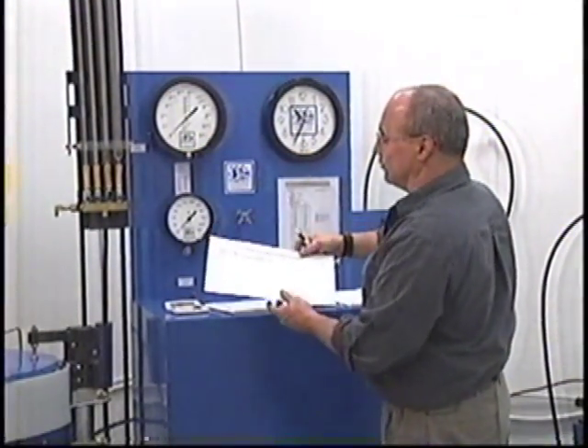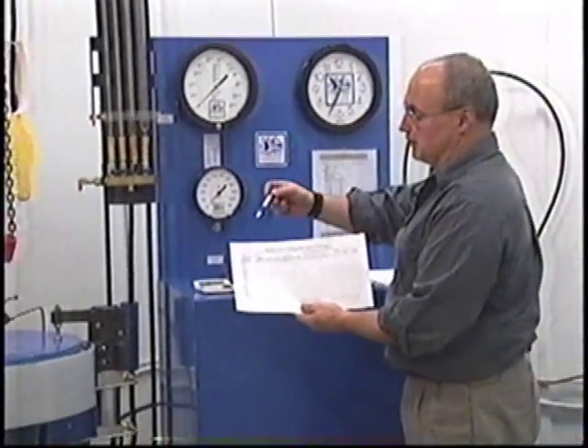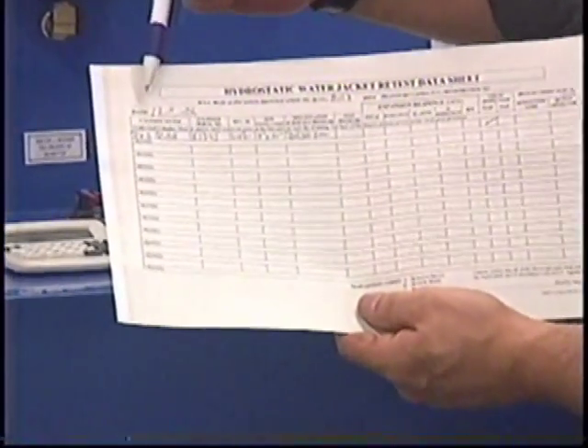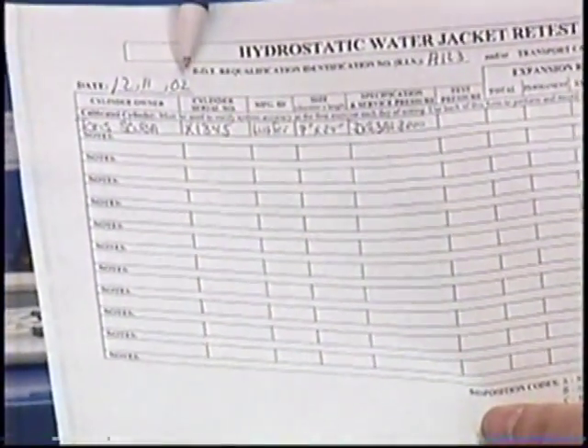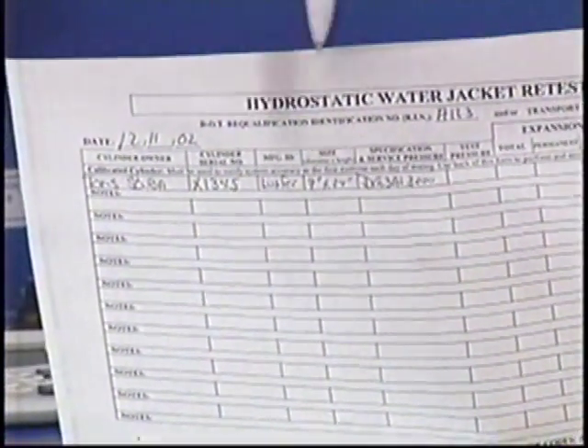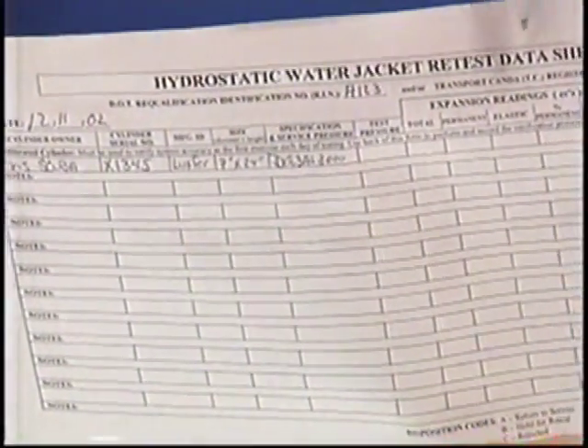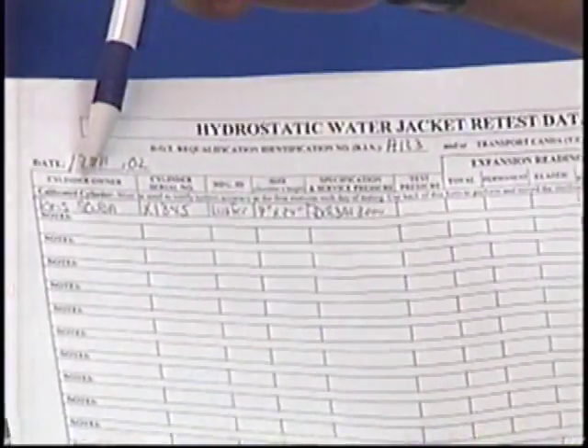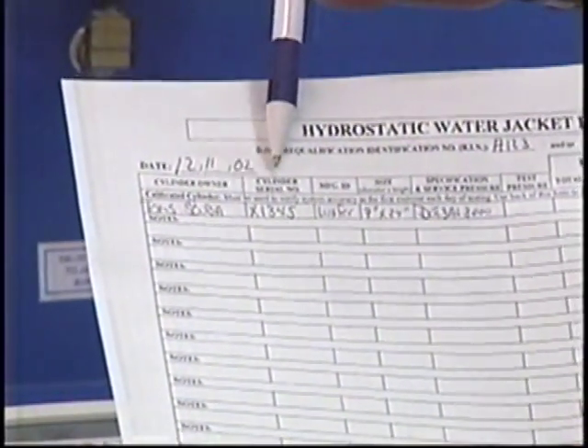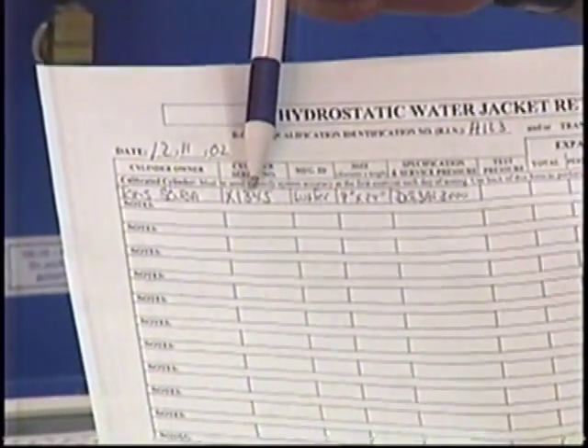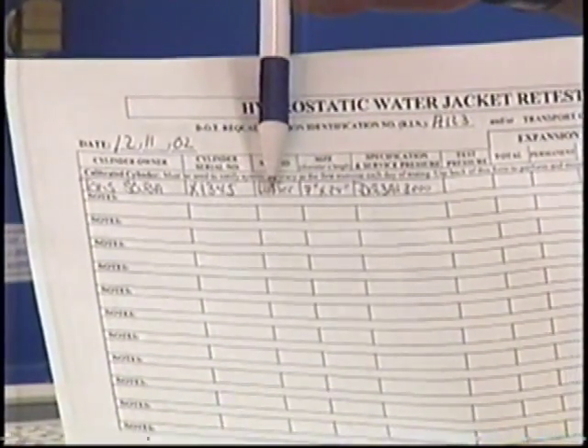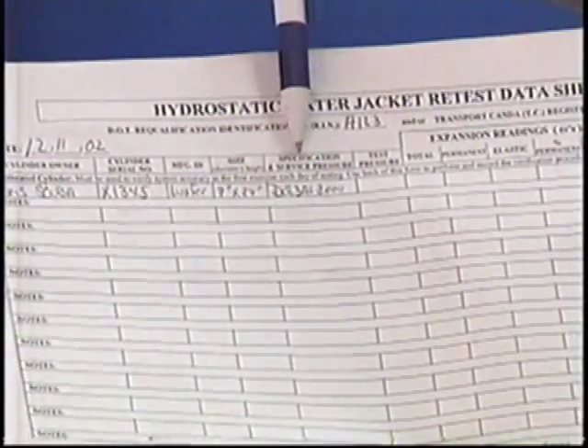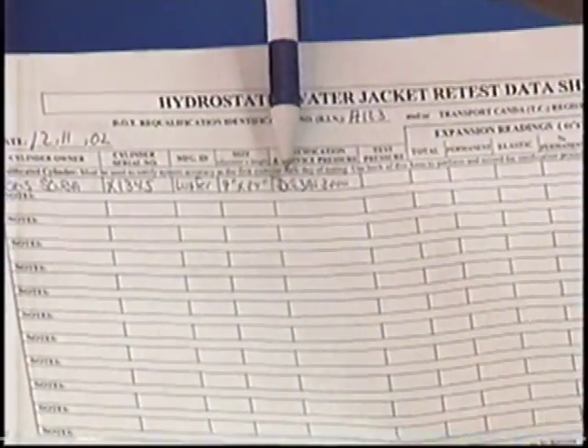The test record form must be filled out for each and every cylinder that you are testing that is DOT or Transport Canada rated. The date corresponding to your verification form, your DOT number or your Transport Canada number, the cylinder owner, the serial number of that cylinder, the manufacturer's ID, the size, which is diameter by length, and the specification service pressure.